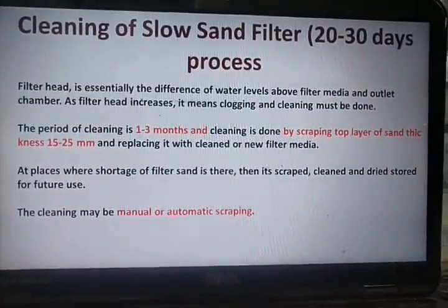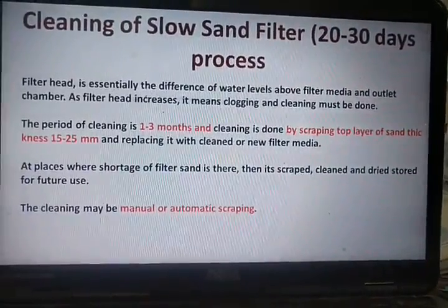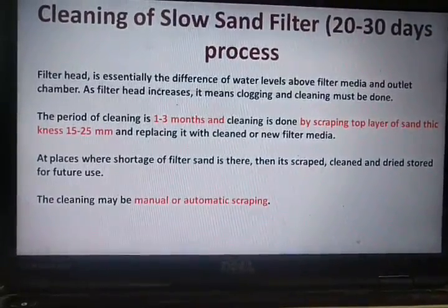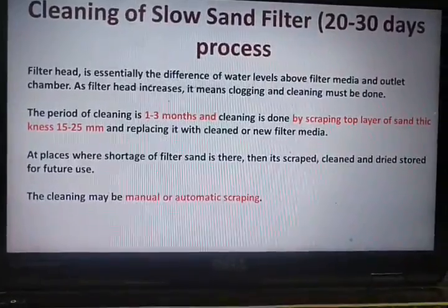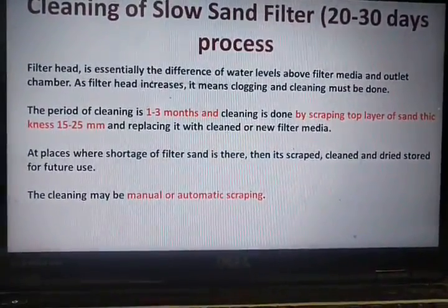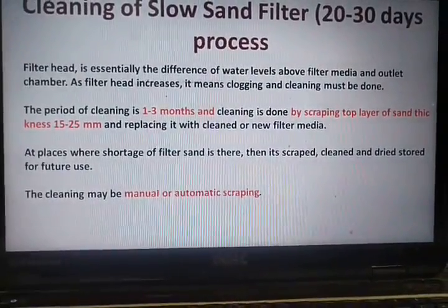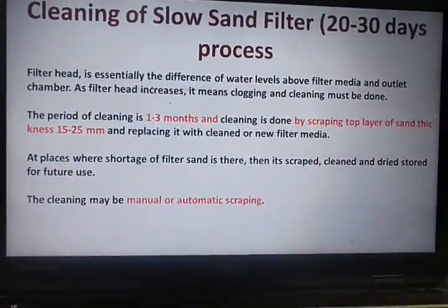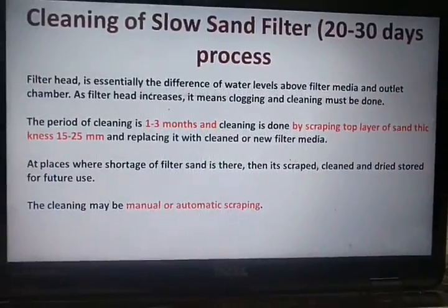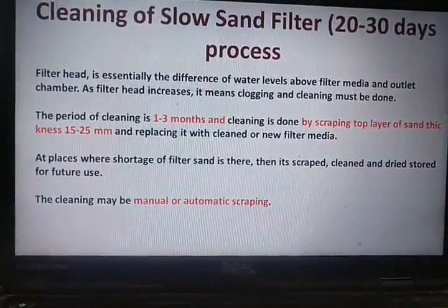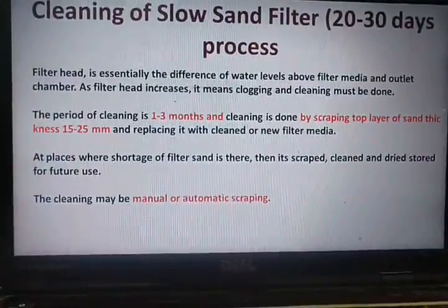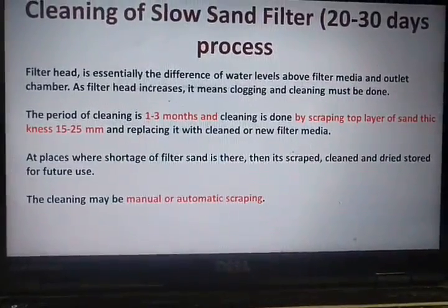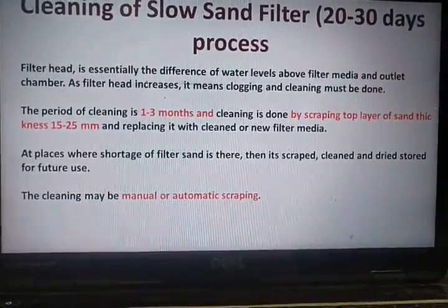Then coming to cleaning of slow sand filter, the cleaning process is usually done once in a month or in between 20 to 30 days. See what happens when the filter is constantly under use, in the initial days of up to 4 to 5 days, the formation of the dirty skin layer starts to appear, okay, and it becomes a stable layer, and the sequence of treatment operation will be very good and it will have very good efficiency.